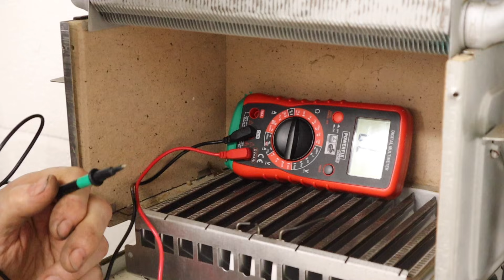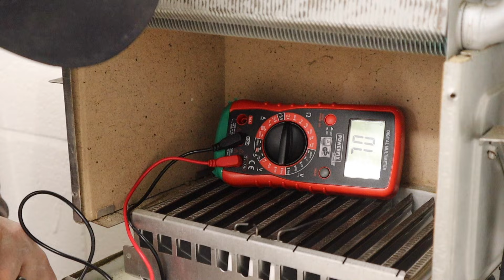Now I've cleaned the probes up, so these are ignition flame rectification. Let's just test the lead. If we go at the bottom here and the end, we should get a buzz. So we're okay on that one. Let's try this one. Yeah, we're good on that one. Try not to get in the way so you can see it. Yeah, we're very good, so now they're cleaned up, they're okay. It's not saying we're not getting a signal down the bottom, but we certainly are along the top, so they're not insulated. That's a good thing.